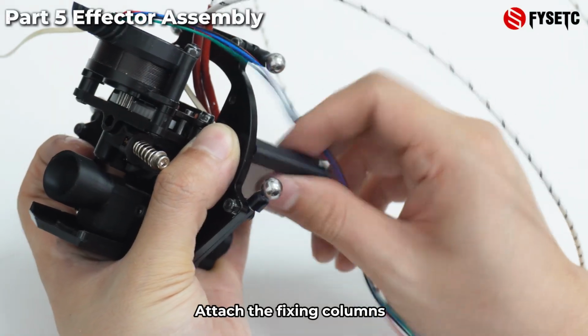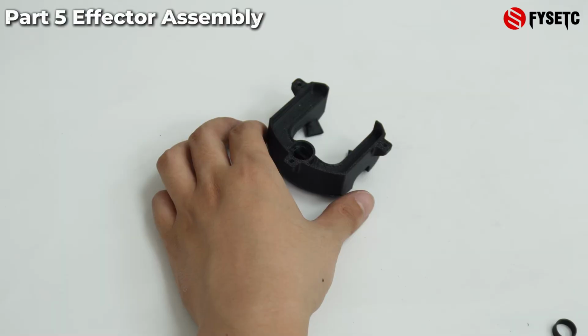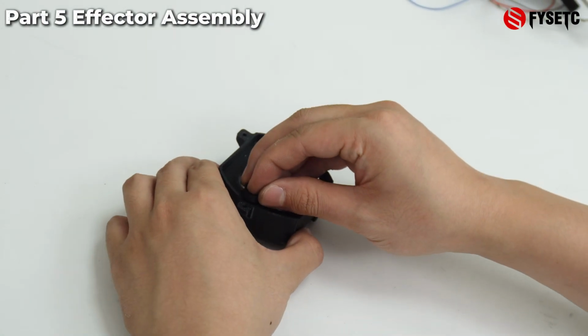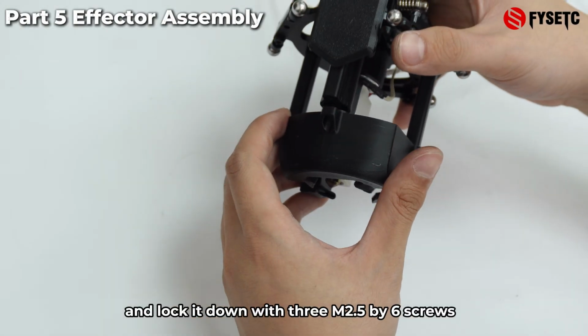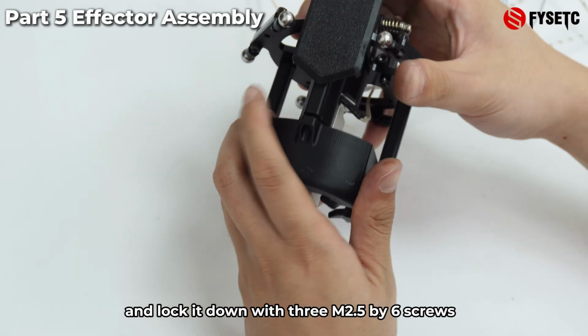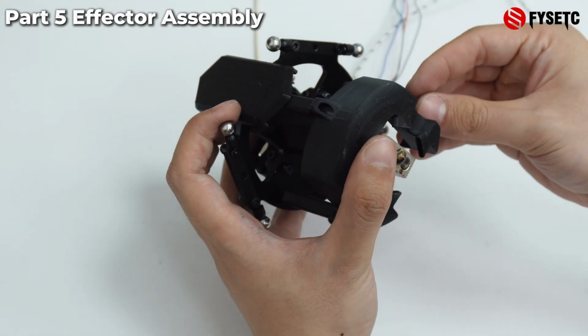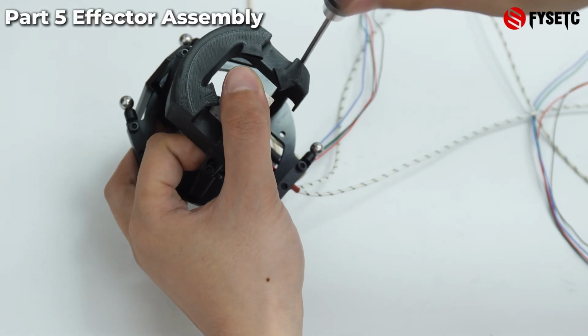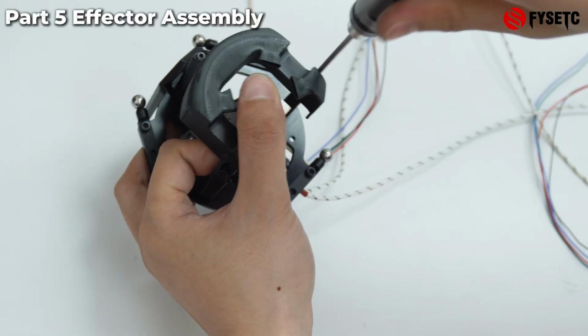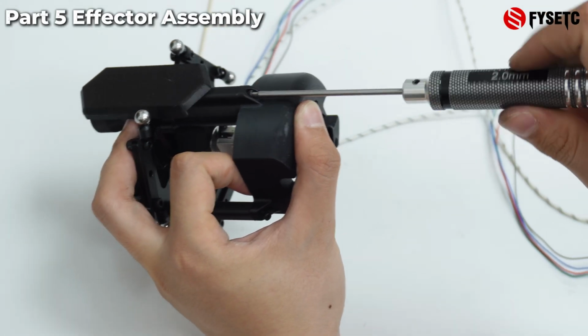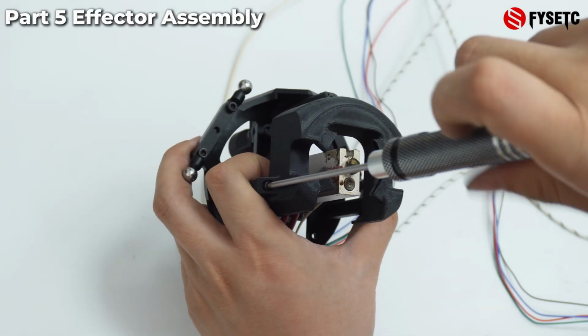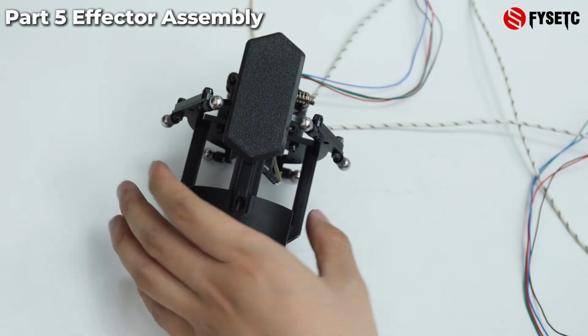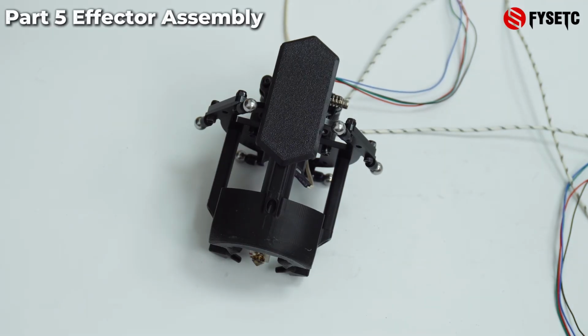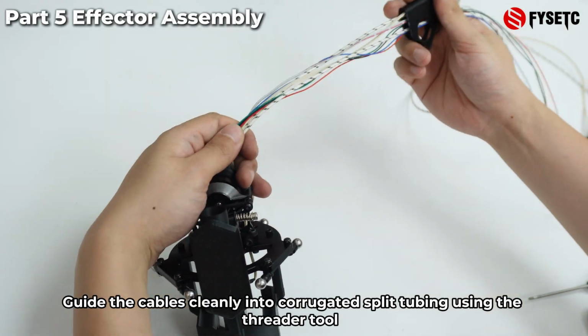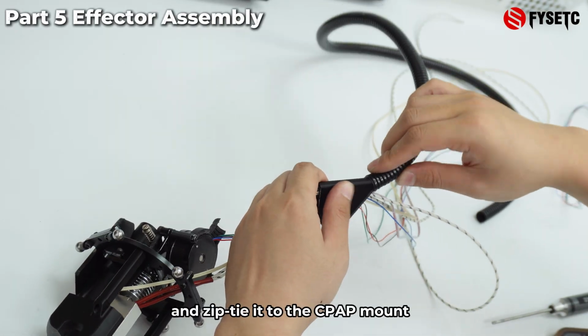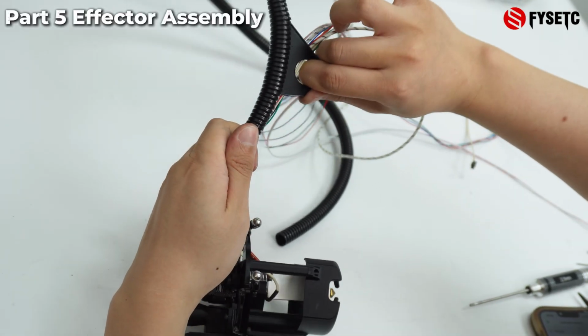Attach the fixing columns. Insert the air blocking ring and lock it down with three M2.5 by 6 screws. Guide the cables cleanly into corrugated split tubing using the threader tool and zip tie it to the CPAP mount.